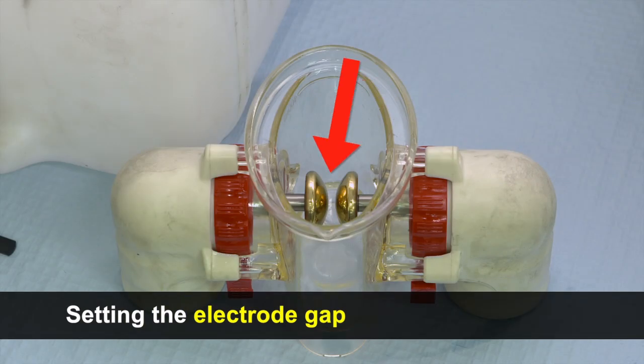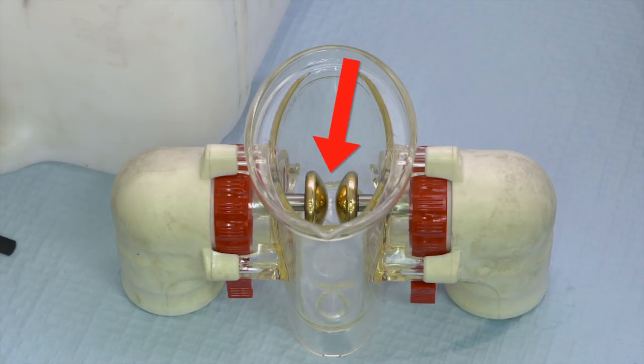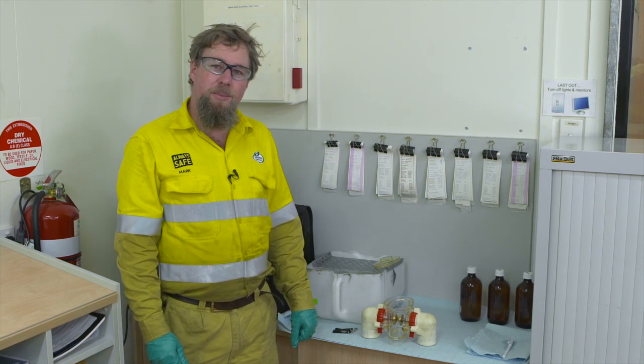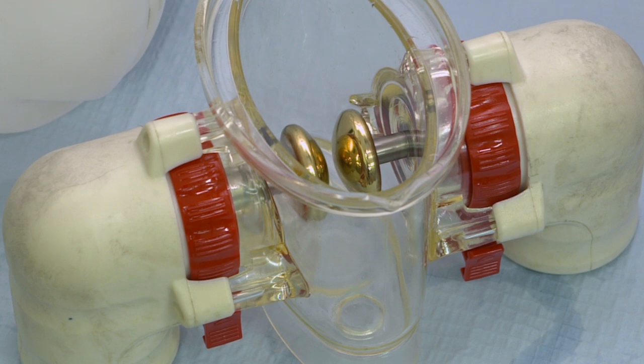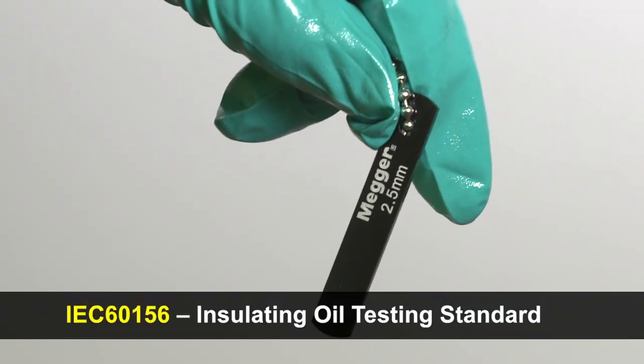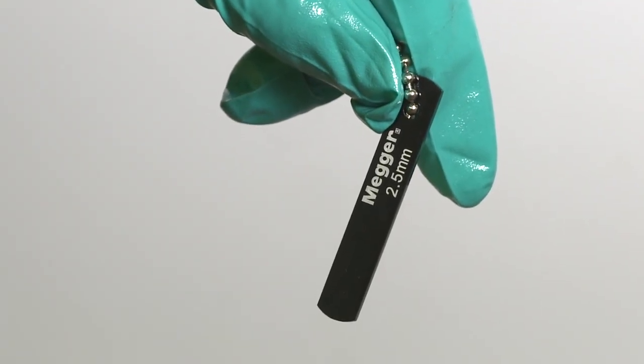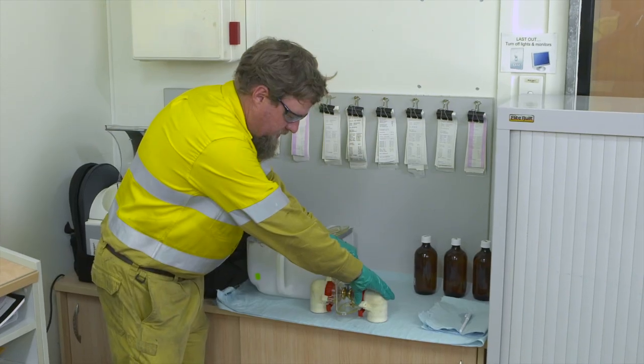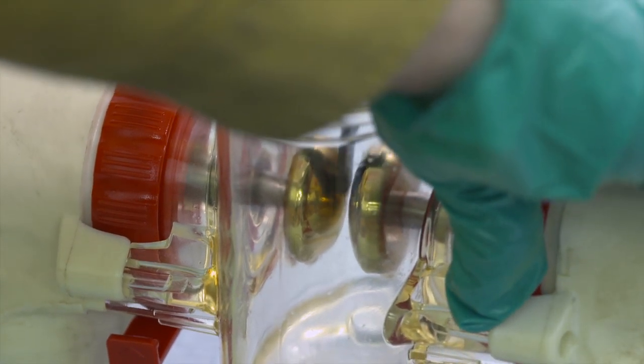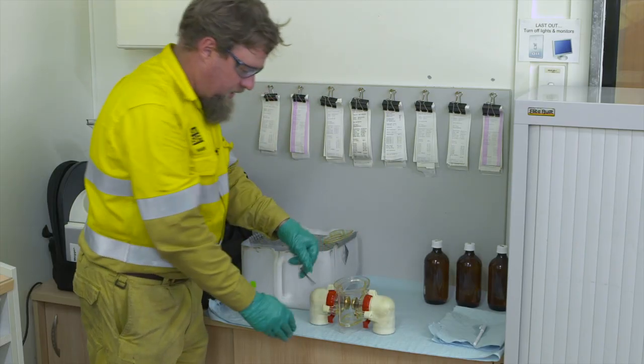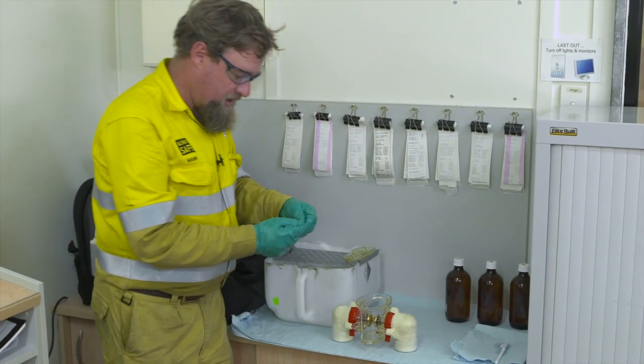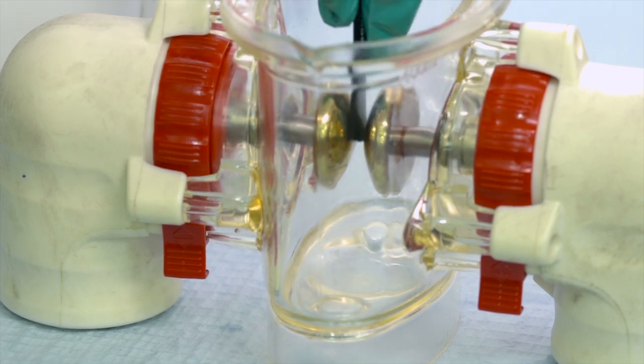Before sampling, it's important to set the electrode gap. If the electrode gap isn't set properly, it'll give you a false reading. So it is very important to make sure that the electrode gap is set perfectly. The standard that we use for the oil is IEC 60156, which requires a 2.5mm gap between the electrodes. So you put that down between the electrodes, and twist your electrodes till it is just grabbing on your spacer. Once that is set, there are 2 locking tabs underneath to lock it in, and then retry just to make sure it hasn't moved.